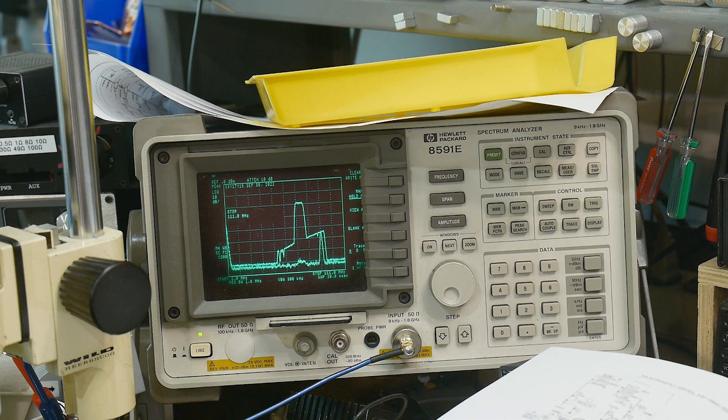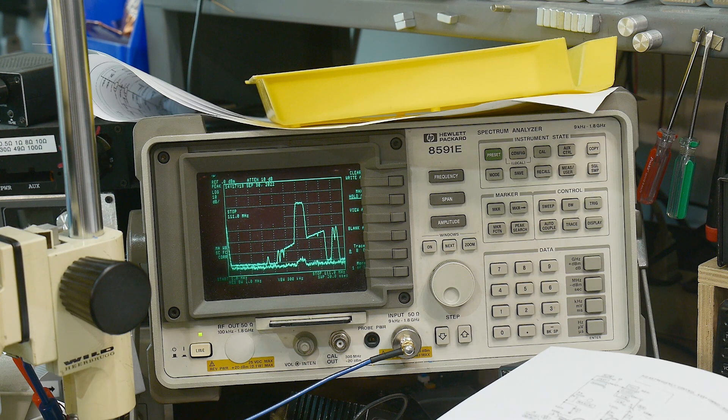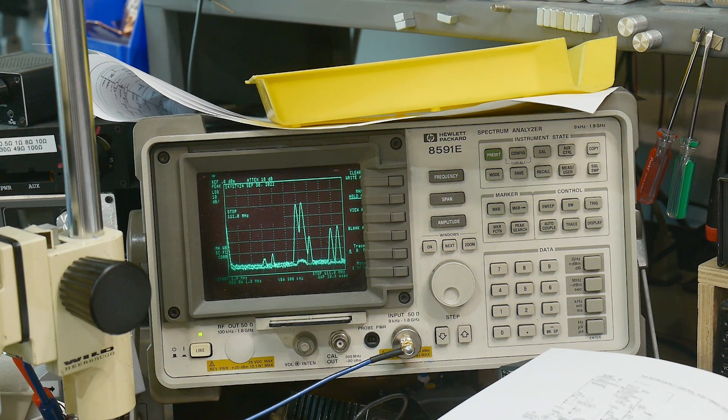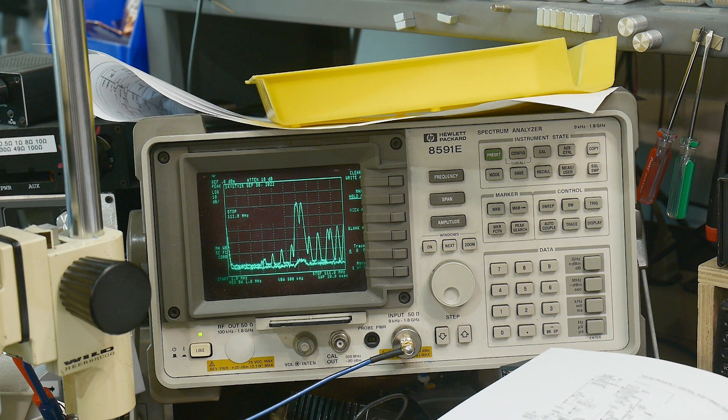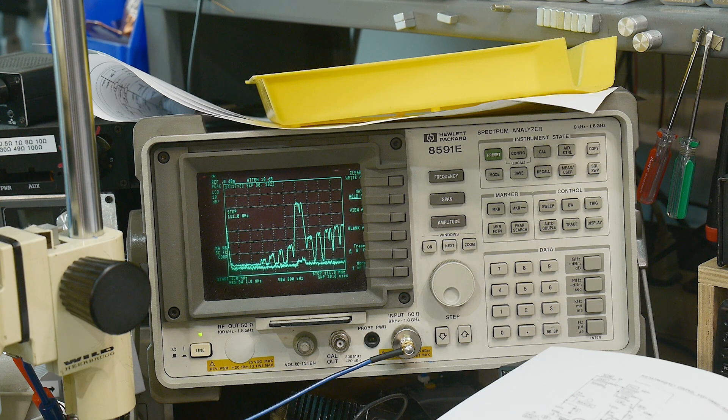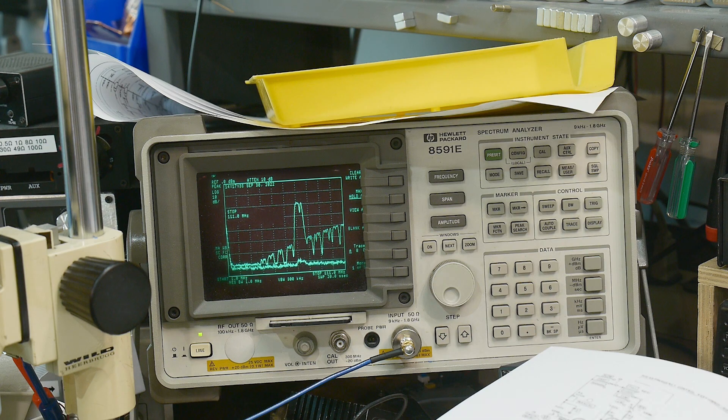So if I just put it on fast, it's going to take it a while to build up the whole picture. If I start it over here, it sometimes guesses right and sometimes guesses wrong. It's all by luck. So you want to have a slow ramp if your spectrum analyzer is not synchronized. You don't have a tracking generator synchronized to your generator.